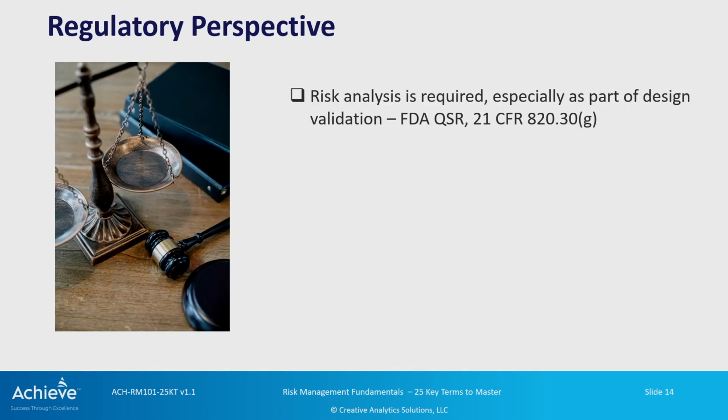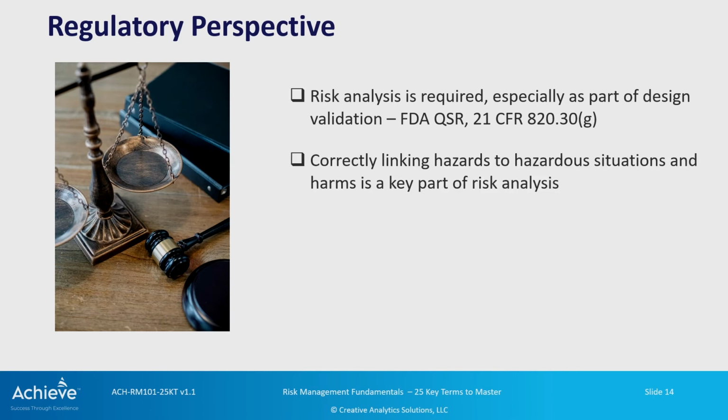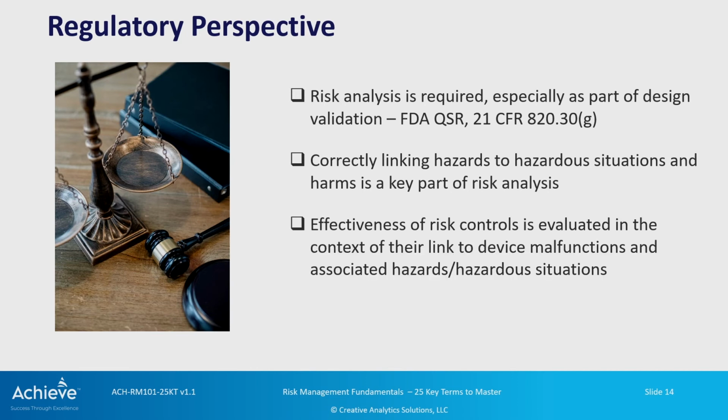Now, the regulatory perspective is that risk analysis is required as part of design validation, and this risk analysis should include understanding of hazards, hazardous situations, and harms. Correctly linking hazards to hazardous situations and harms is a key part of risk analysis. That's why that linkage becomes very important. And effectiveness of risk controls is evaluated in the context of their link to device malfunctions and associated hazards and hazardous situations. It's a linkage, not necessarily a direct one-to-one cause and effect. That's the key point to keep in mind.